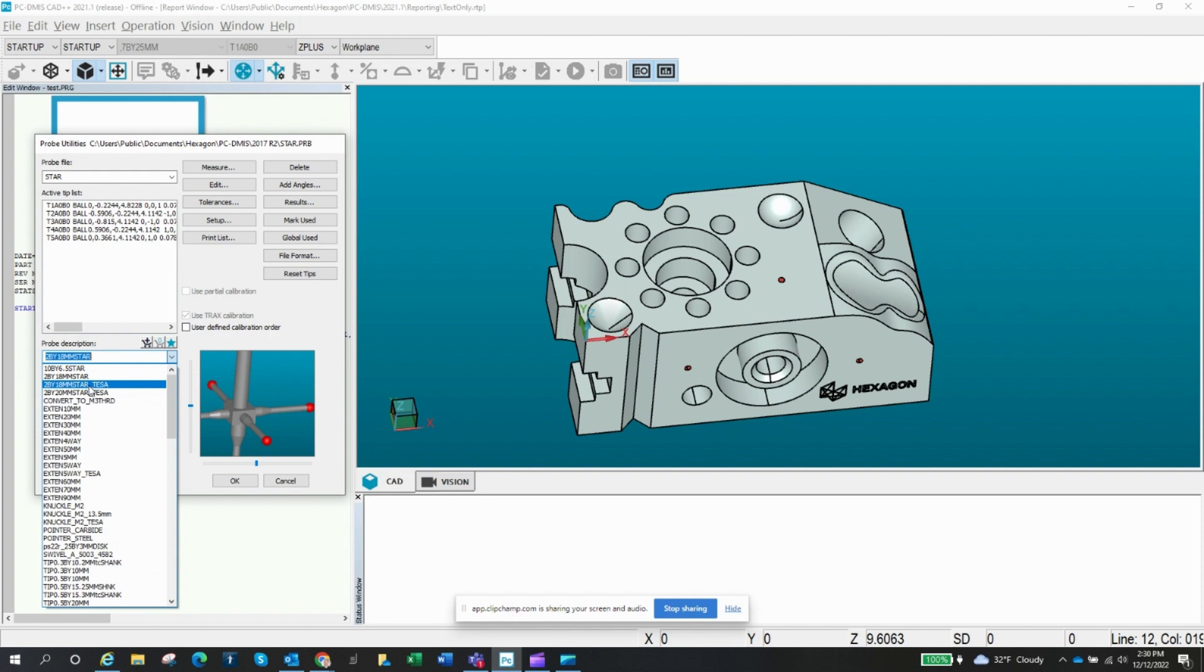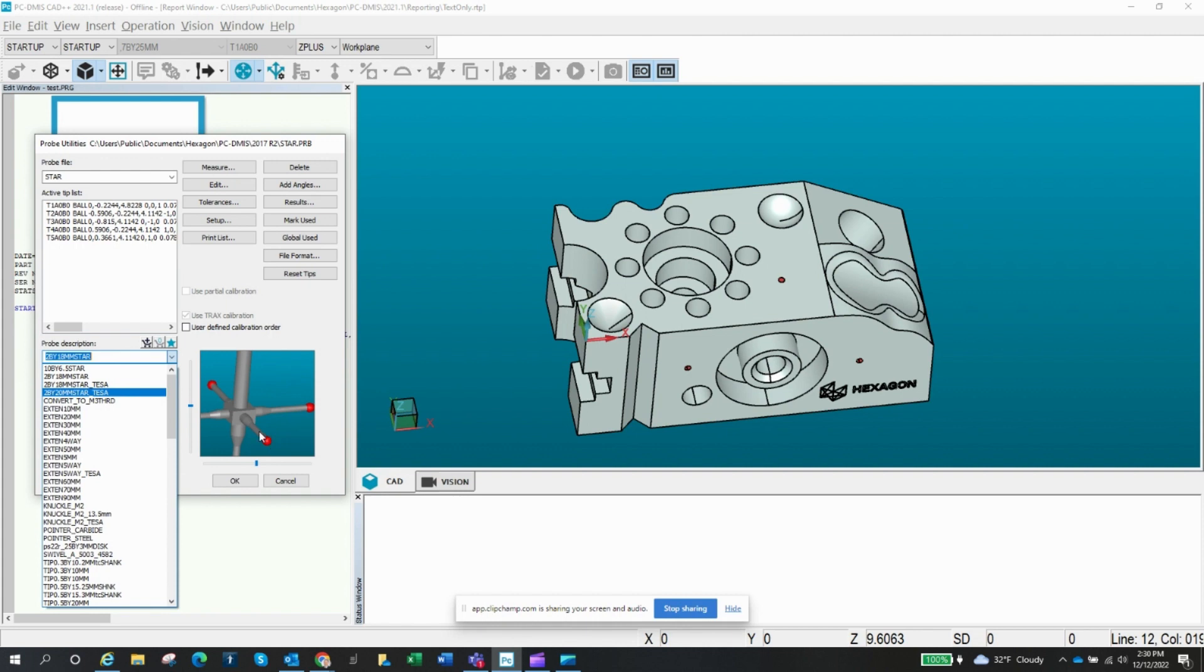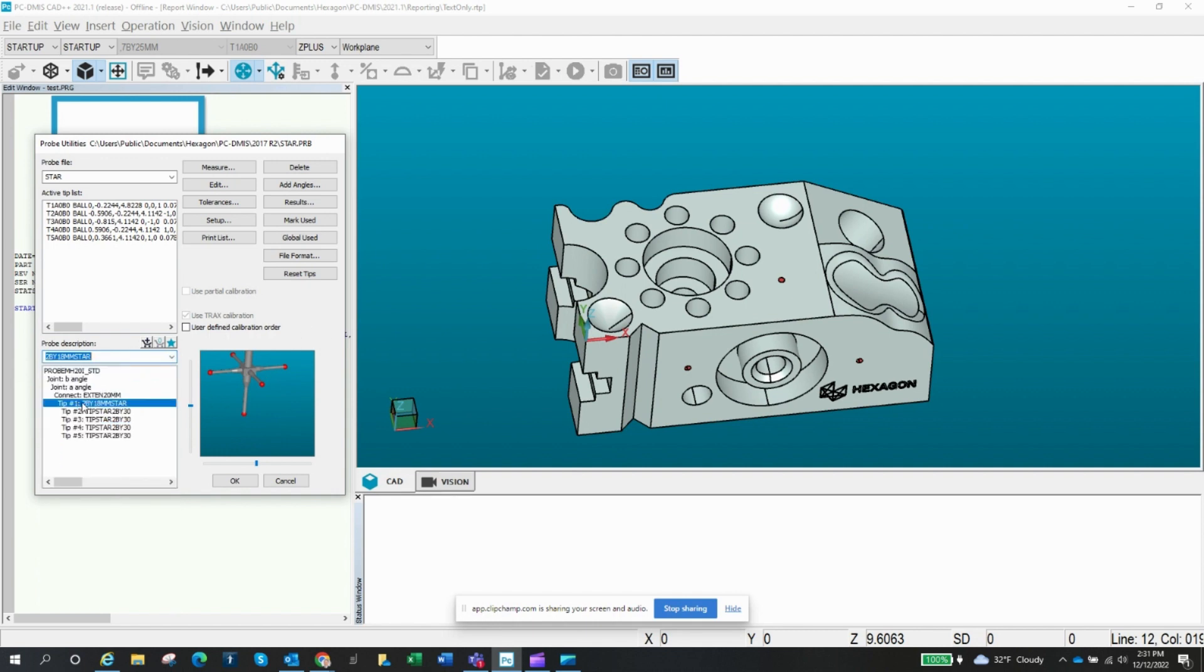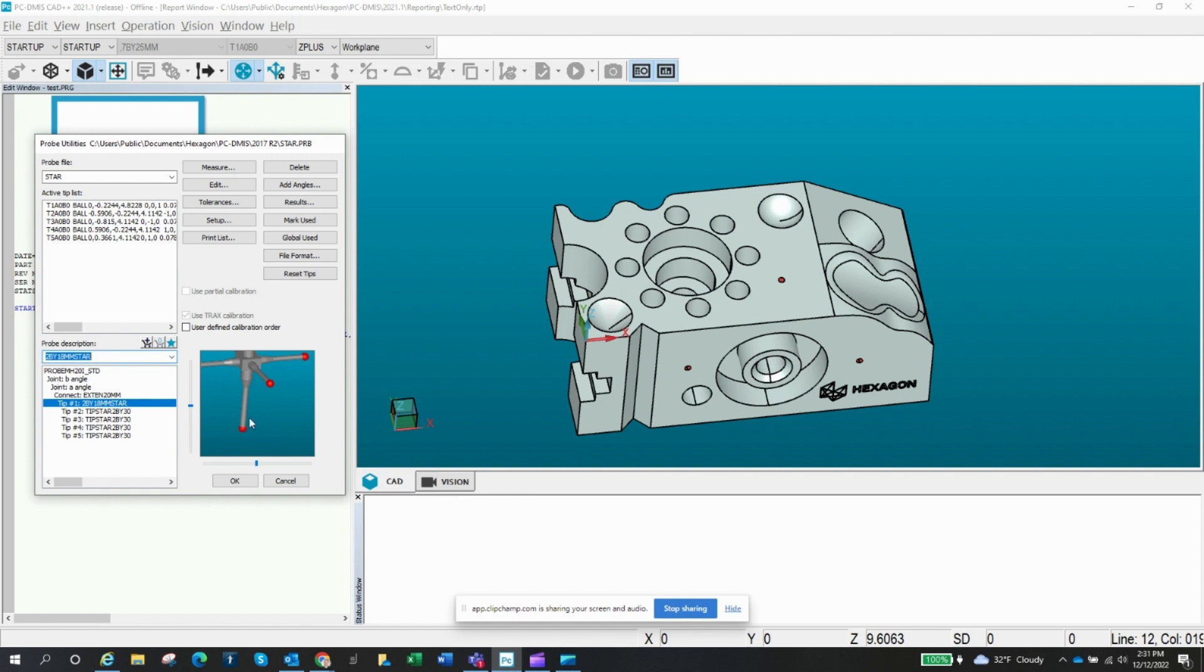Now just select the one that's closest. You may not have it exactly right and that's okay. Get as close as you can, as far as obviously the diameter of the ball or the stylus, and then the length. So that's what's important. And also, if you go back to this, you'll look, so you've got tip one through five. So tip one is this one that's going down. And that's what's important. So that length is going to be this standard length here, right? So basically your connection to the center of the ball is that 18 millimeters. So that's the first step.